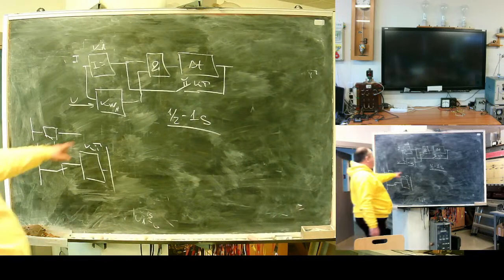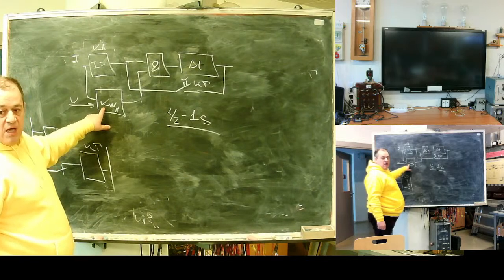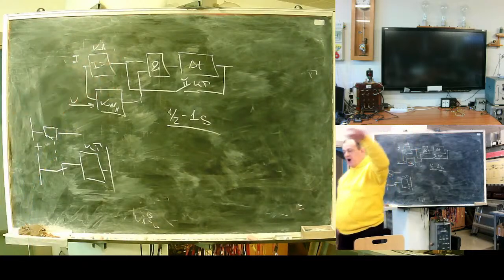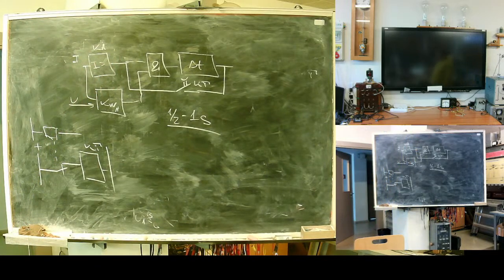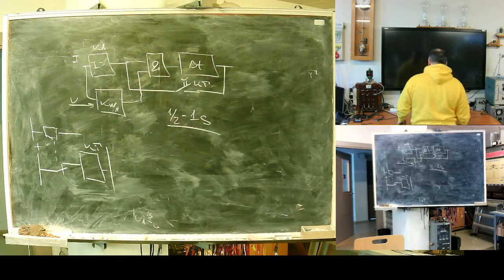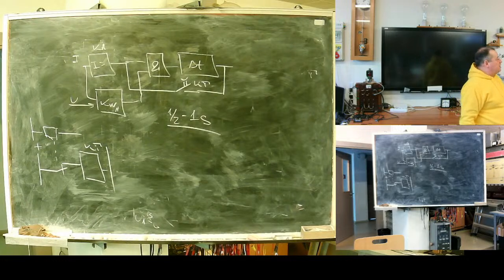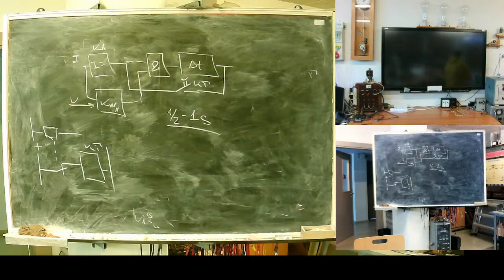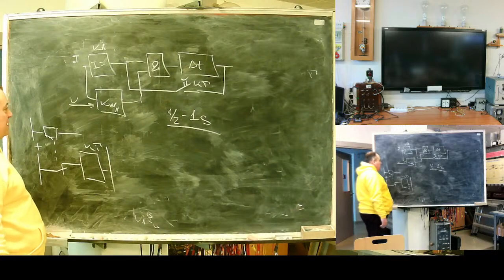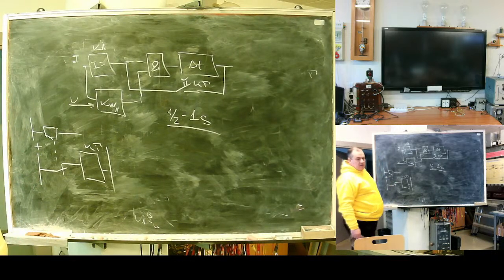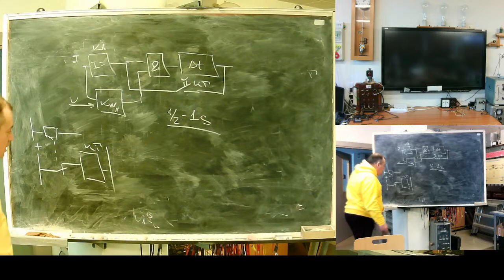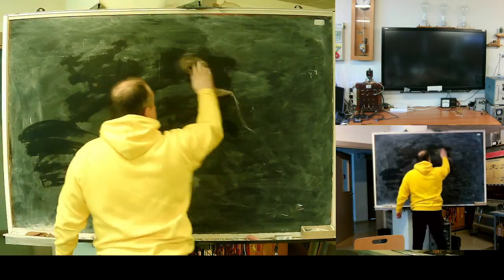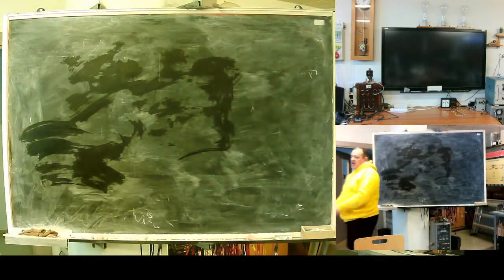In case you have a fault at 0 kilometer, it will operate because the power direction function is bypassed. If you have a fault at the far end of the line, there is no need to wait. In case of switch on fault, protection trips instantly. It was this bypass circuit. It's an old, well-working solution. In modern digital relays, a bit different approach is used because there is no easy way to create a bypass and not necessary second zone.